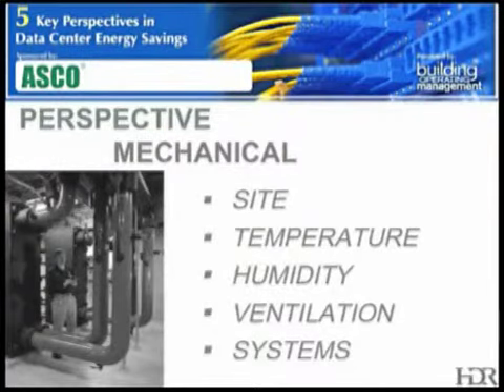Now, you can certainly enhance the efficiency of these systems if you're able to provide airside economization to either these CRAH or CRAC units, which there are some components that add a mixing chamber above them if you have access to exterior outside air. And of course, the addition of a water side economizer to even an air-cooled plant will certainly help if you've got the right climate. You can do that with either just pure dry coolers or possibly an evaporative fluid cooler to provide a lot of free cooling during the colder temperatures.